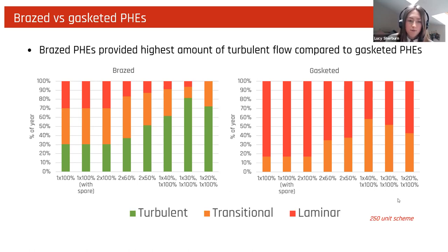So we want as much turbulent flow as possible. So using the hourly load model at each load point within that, I was able to tell whether the plate heat exchanger selected was operating at turbulent, laminar, or transitional flow. And transitional flow is just the bit between the two there. The graphs compared different size plates for both brazed and gasketed solutions. And you can see the breakdown of those different flow regimes across the year.